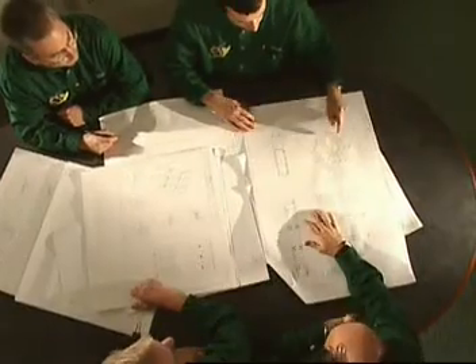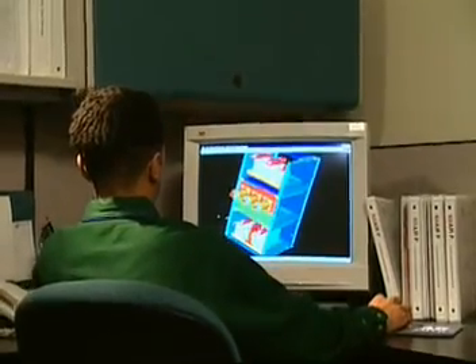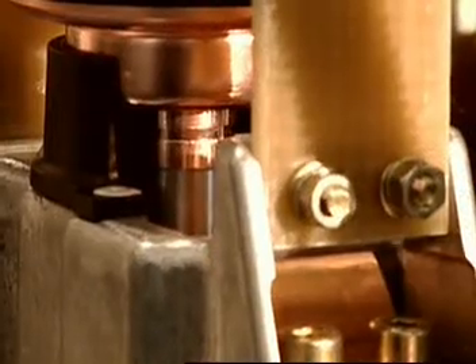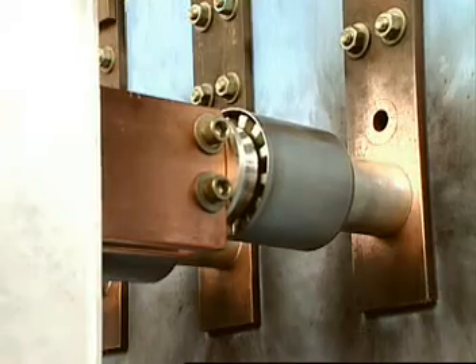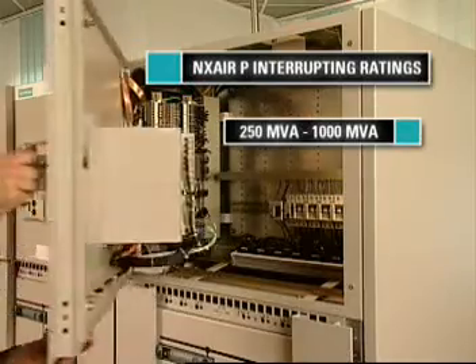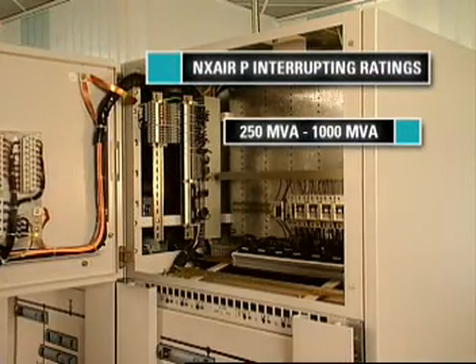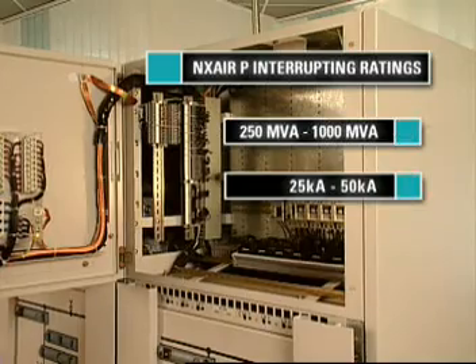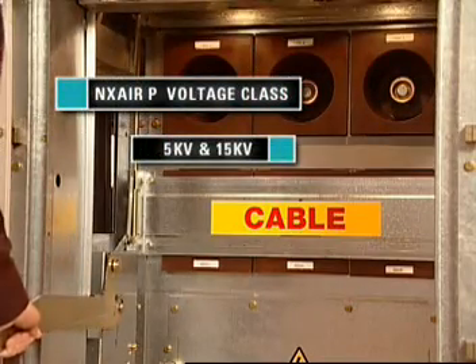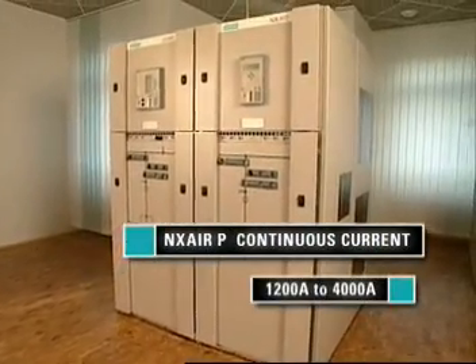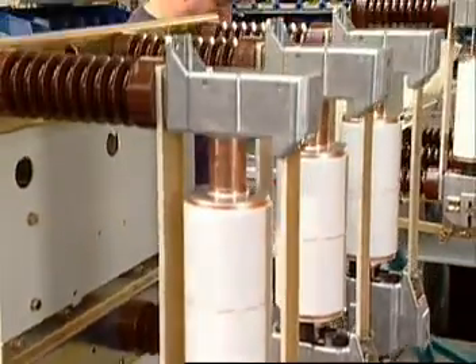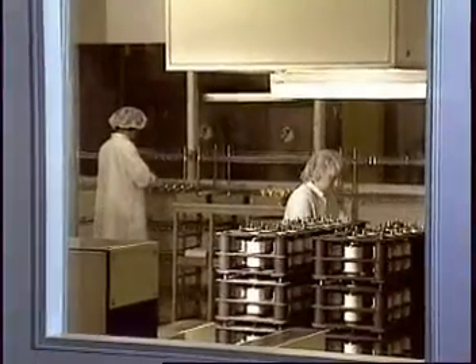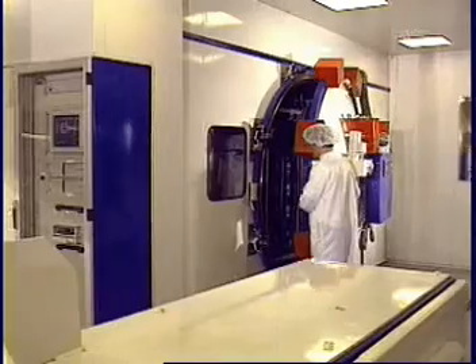Siemens saw the need for a new kind of switchgear to meet the challenges of the changing market. So we asked our American customers what they wanted, and we designed the NXAirP with their input in mind. Siemens invested 3 years of research, development, and extensive testing to create switchgear that meets the needs for the future. The NXAirP has interrupting ratings of 250 MVA through 1000 MVA and 25 kA through 50 kA, a voltage class of 5 kV and 15 kV, and a continuous current of 1200 amps to 4000 amps. As the name implies, the NXAirP is air-insulated switchgear with vacuum interrupter circuit breaker technology.